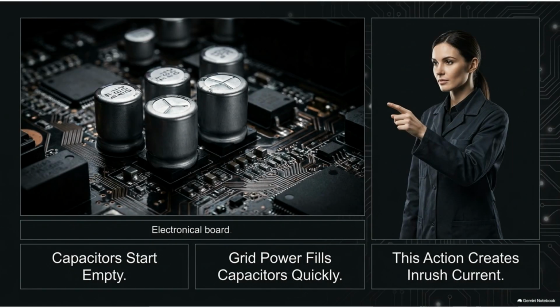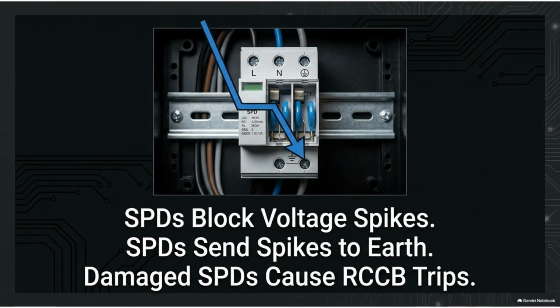Electronic boards often contain capacitors that start empty. When power returns, these capacitors fill quickly, creating a sudden inrush current that can cause the RCCB to register an imbalance. Surge protection devices, or SPDs, are designed to block voltage spikes by sending them to earth. However, if an SPD is damaged, it may leak enough current to trigger the RCCB.